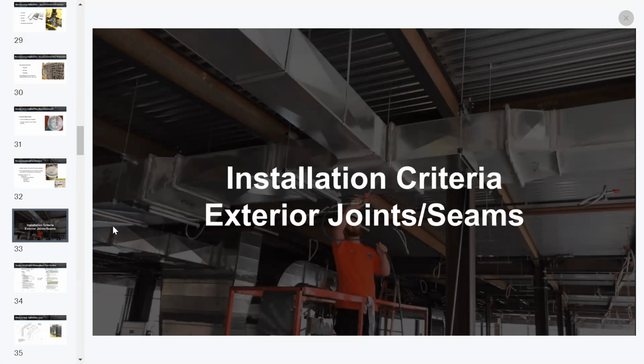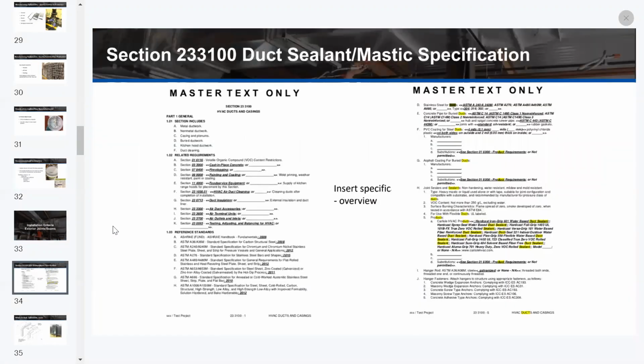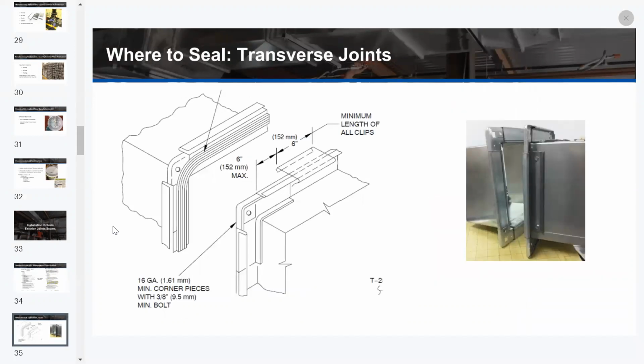So let's talk about some installation criteria for the sealants. It's key to utilize specifications to define your requirements of product performance, specific needs, testing protocol, etc. Here's just a couple examples of sealant specifications. When we're talking about transverse joints, we know the transverse joints must be sealed once they're assembled on the job site, right? In the left picture, the gasket is shown following a nice radius around that corner. Ideally, applying the sealant with a loop in the corners and tucking it over helps seal those corners appropriately. Most 4-bolt flange manufacturers and most shops that manufacture these cut back that corner to make that easier to install, and that tends to be a very specific leaking point.